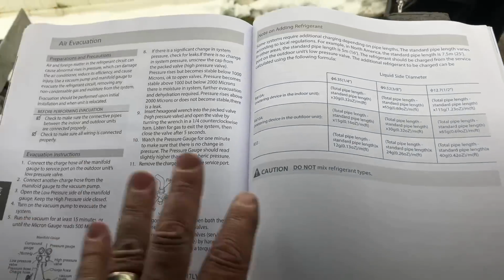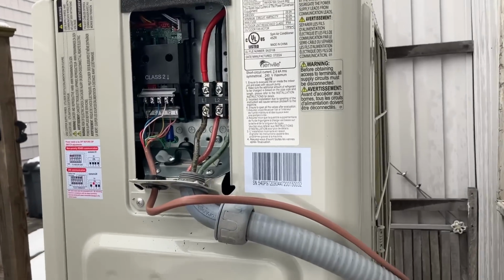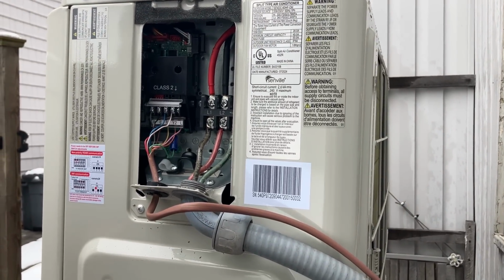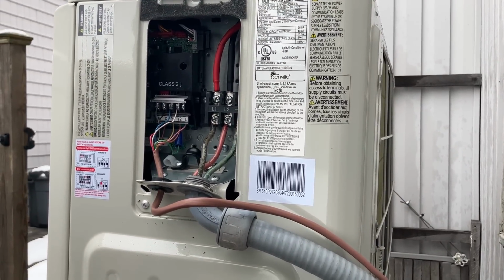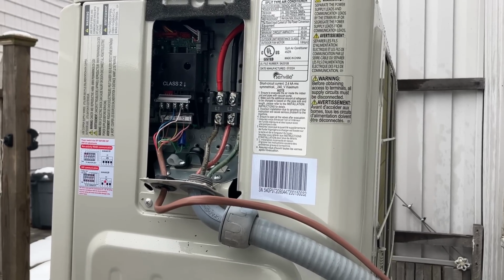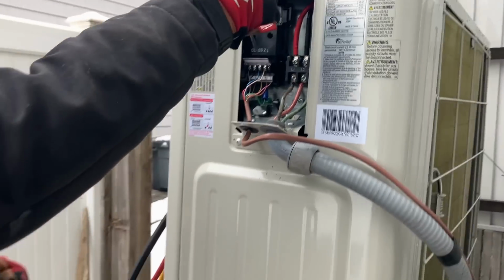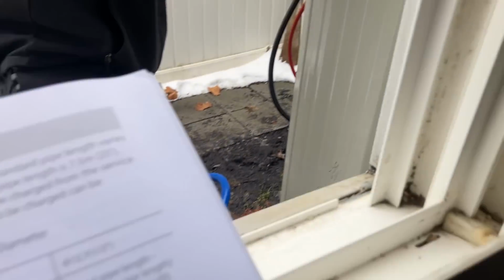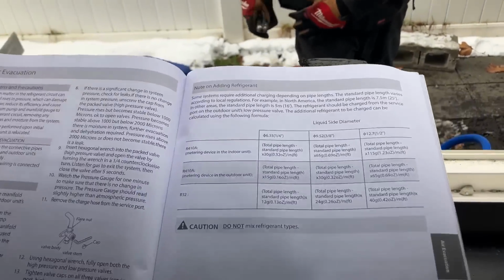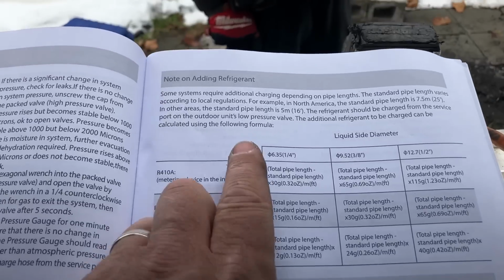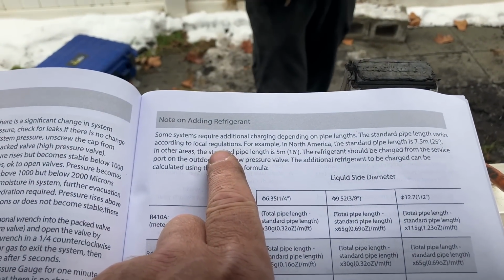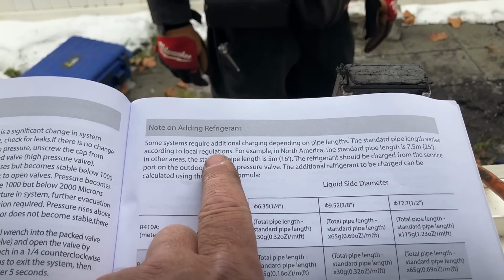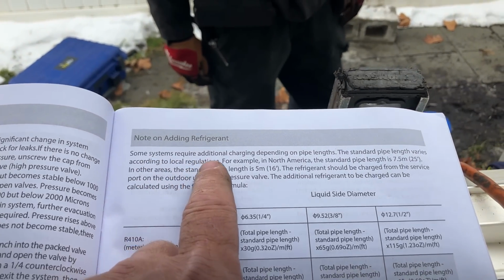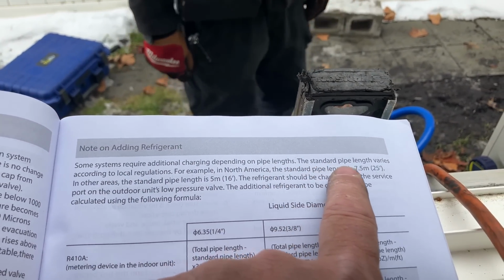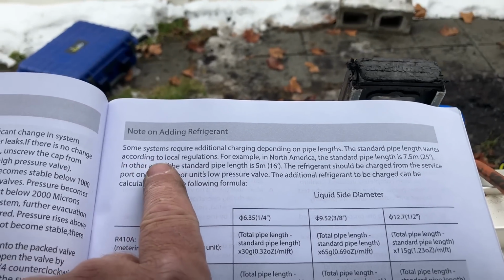We're looking at adding refrigerant, because there's a note here. You can see there, it says to make sure the additional amount of refrigerant to be charged is based on the pipe size and length. Refer to installation instructions for details. And if it's an incorrect installation, we'll mess things up. So we're going to page 25 of the installation manual for this Senville, and the note on adding refrigerant. It makes kind of sense, but as a professional in the HVAC industry, it's kind of weird. Some systems require additional charging depending on pipe lengths. The standard pipe length varies according to local regulations.